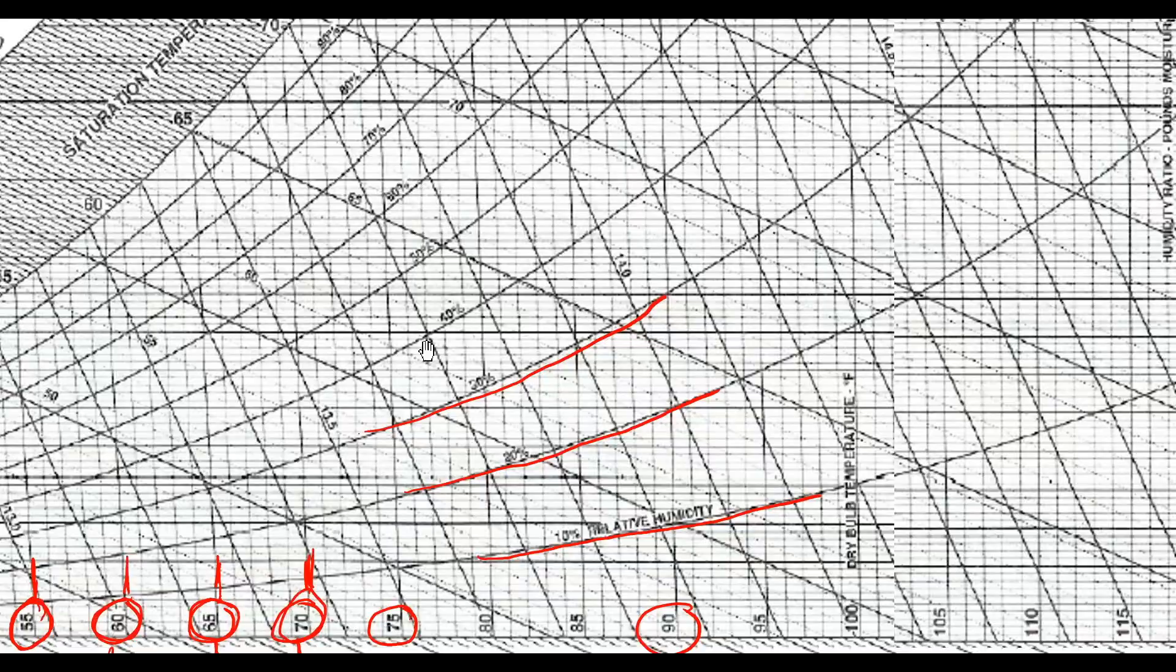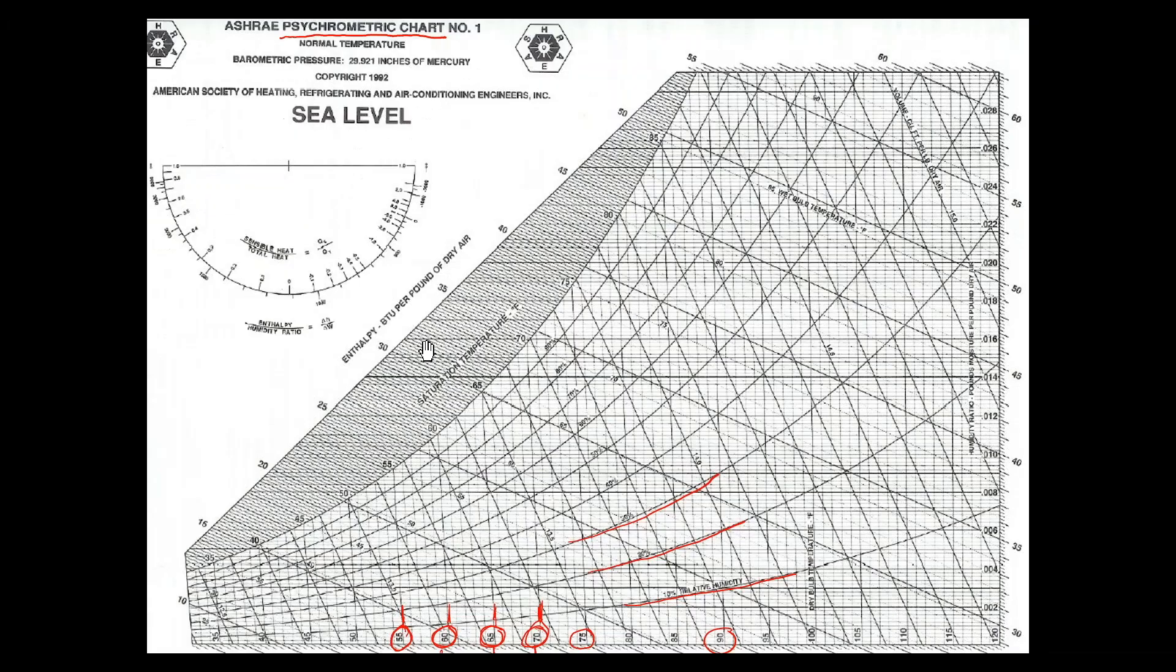Now the final axis we're really interested in is this one over here that's called the enthalpy. That's the total energy content of the air, and the units here are 25, 30, 35, 40. All of these are in BTU per pound of dry air. Now if you're overseas, out of the United States, it would be kilojoules per kilogram.